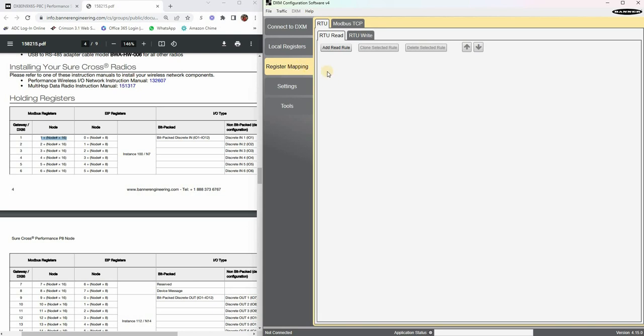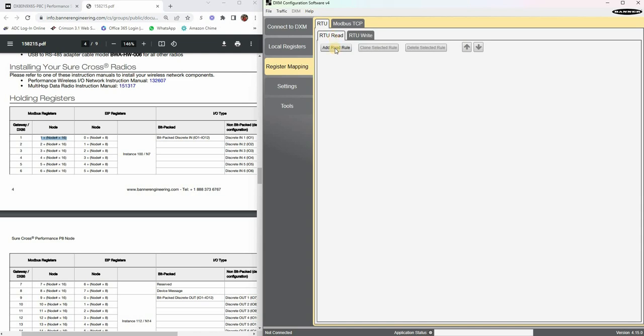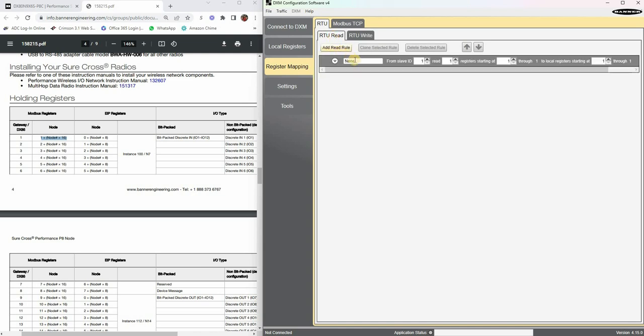But the first thing we actually want to do is register mapping. If the physical input or output is an input, then we want to create a read rule for that. If your terminals are going to be set for outputs, then we want to set a write rule. In this case we have nothing but inputs, so we're going to do read rules. Let's go ahead and add a read rule and we're going to call this node 1 inputs.